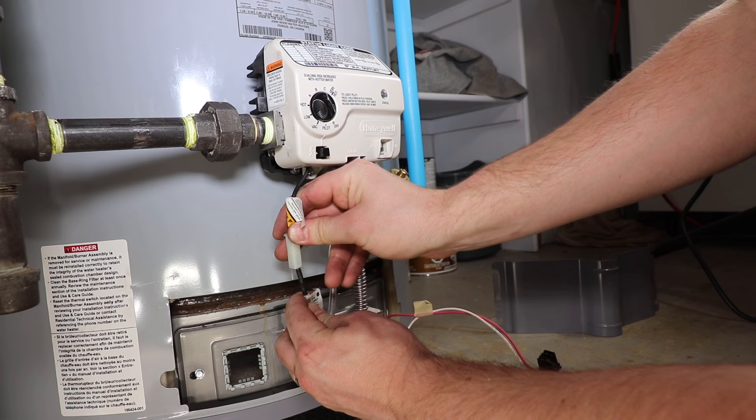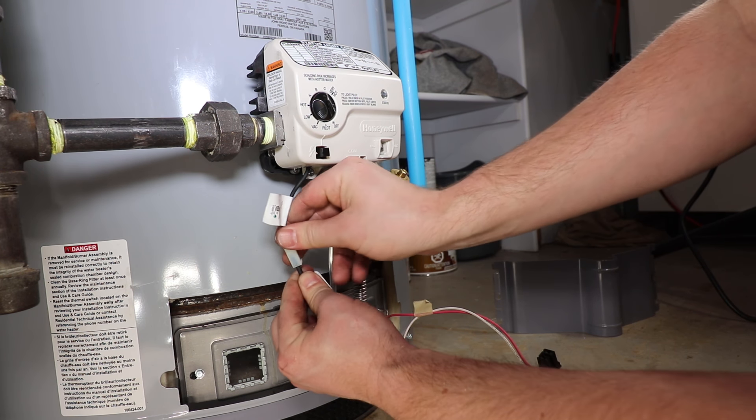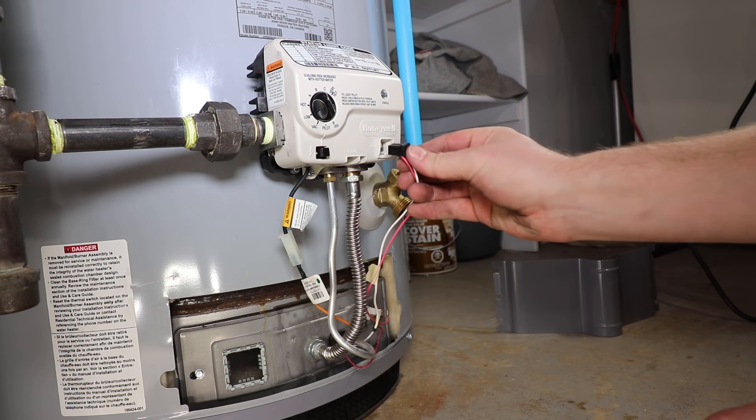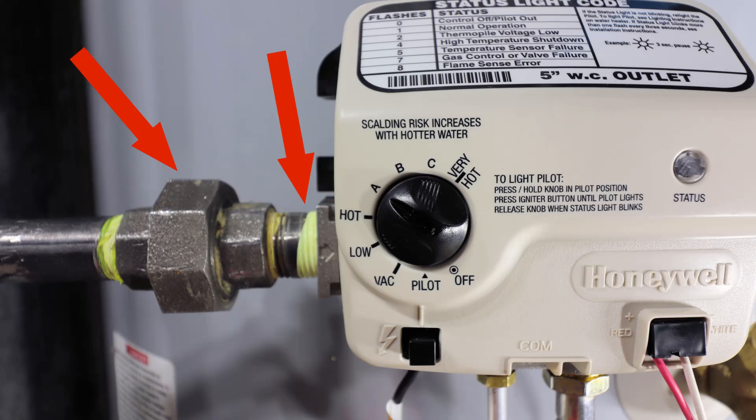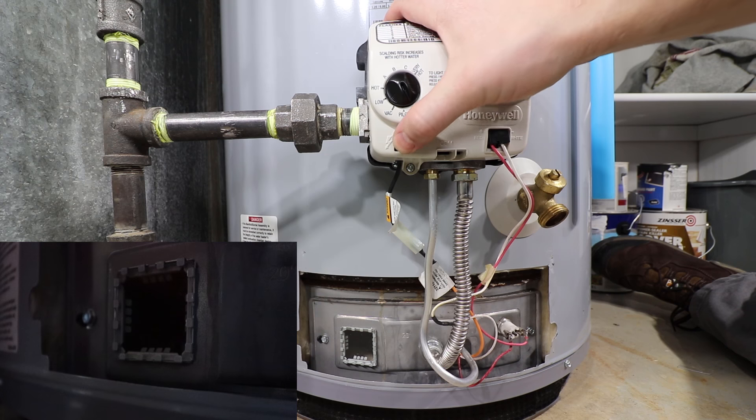Plug the spark igniter and thermopile wiring back in. Turn the gas supply back on to the water heater. If you smell gas at this point, turn off the gas supply and check the union and half-inch gas control connection. You are now at the point where you can relight the water heater.